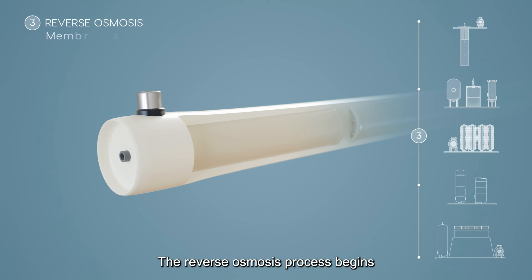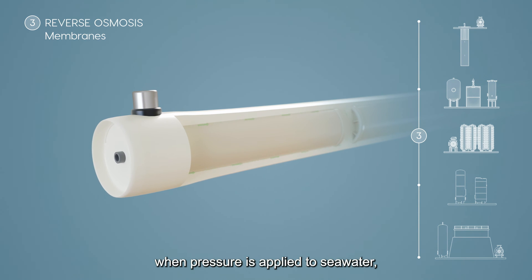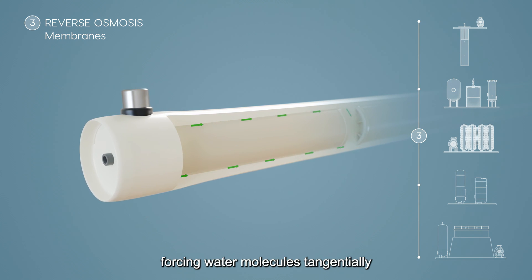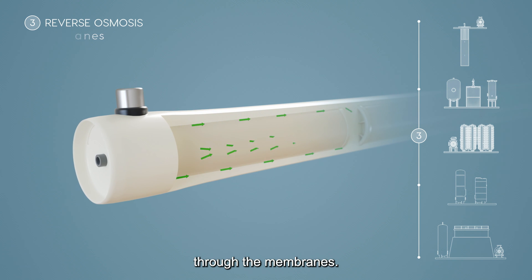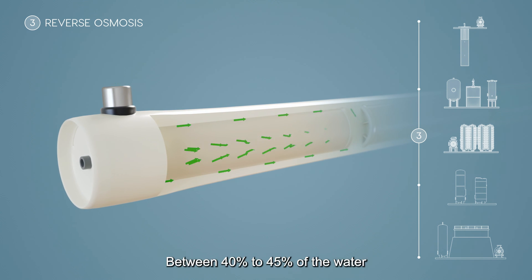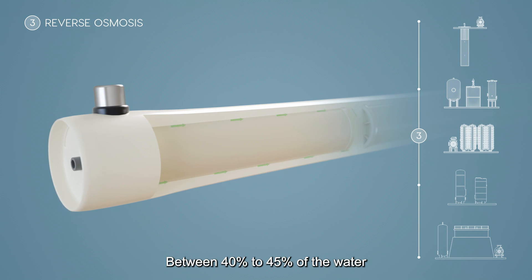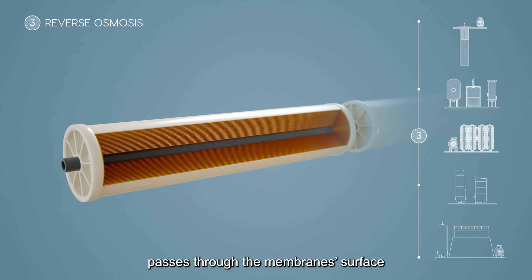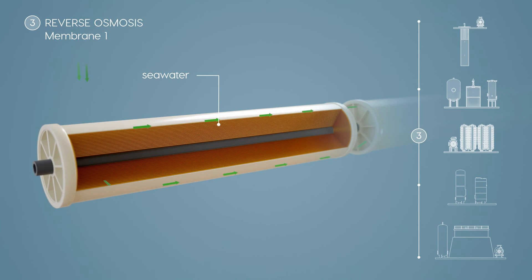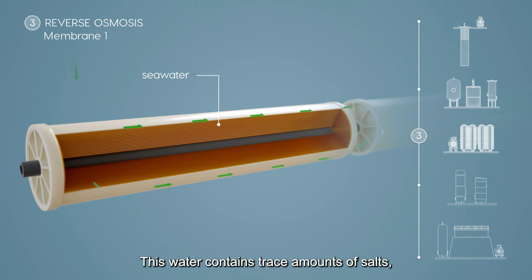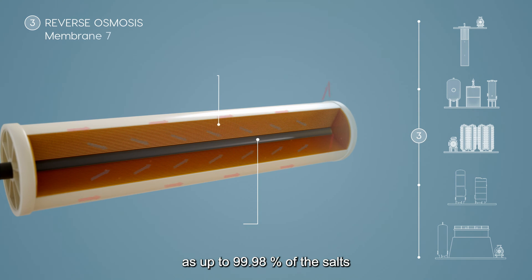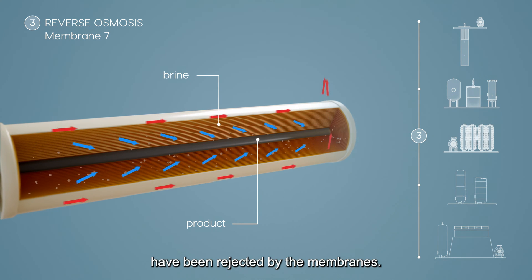The reverse osmosis process begins when pressure is applied to seawater, forcing water molecules tangentially through the membranes. Between 40 to 45 percent of the water passes through the membrane surface and is directed towards the permeate or product collector. This water contains trace amounts of salts, as up to 99.98 percent of the salts have been rejected by the membranes.